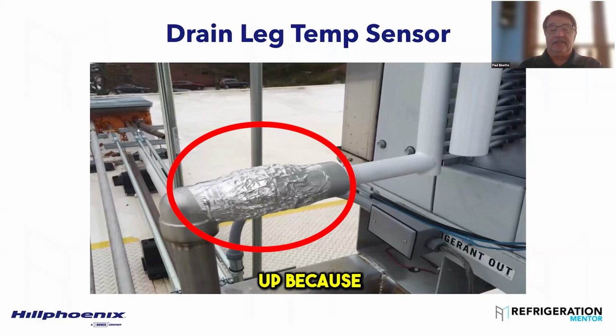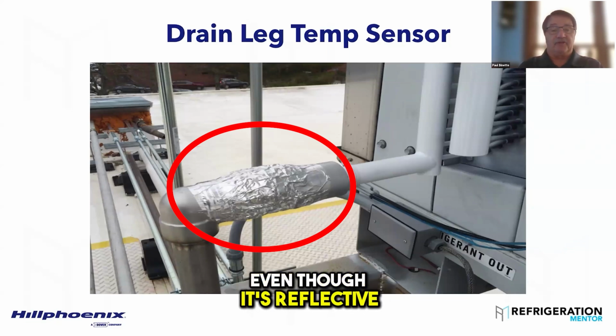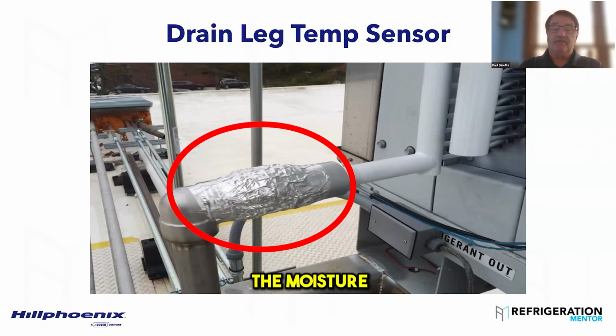I brought this one up because this is a good example of it's okay, but what I like to see is we want to be within 6 to 12 inches of the header, and we want to have 1.5 inches of insulation with a white PVC wrap around it. This is okay, but still it's not enough insulation, and the sun will heat it up even though it's a reflective surface. We want to keep the moisture off of it.